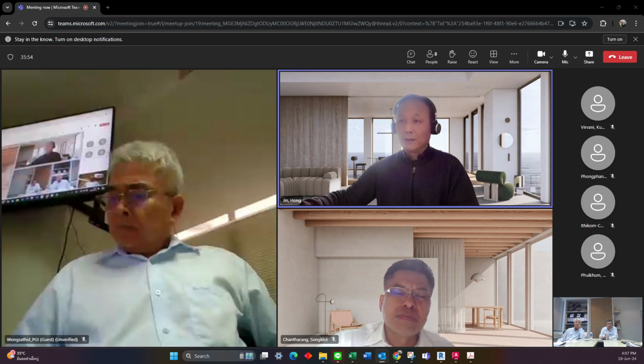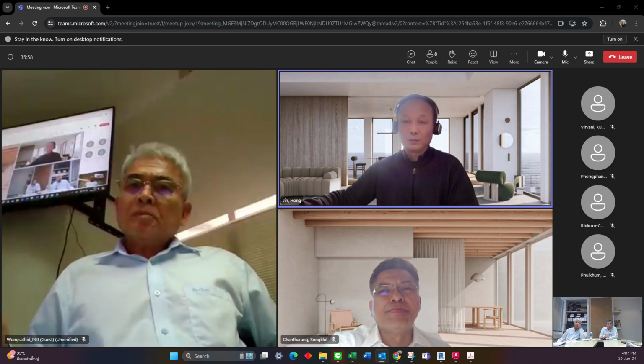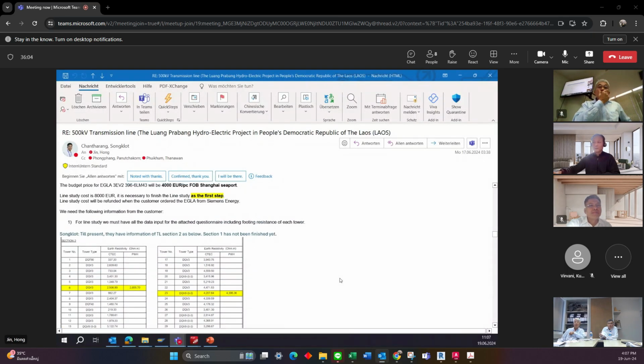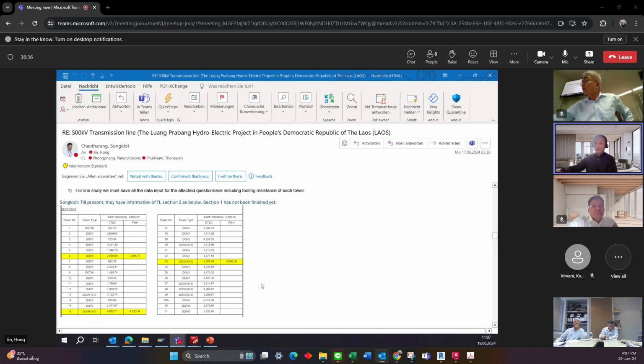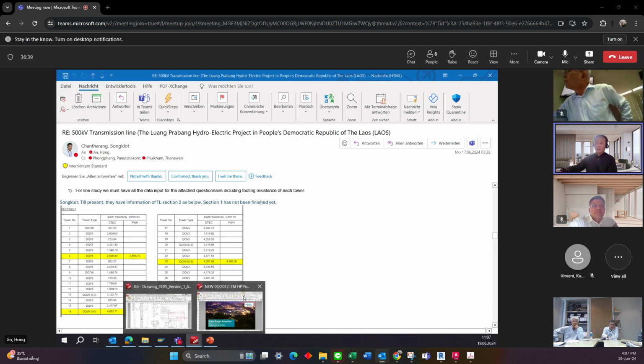Let me share now the reply from the customer side. We have a questionnaire for the line study. As I mentioned, the line study is the mandatory first step. We have so many towers on this transmission line, and for each tower we need the footing resistance, geometry, dimensions of the surge arrester, and also the technical specification of the conductor as well as the insulator itself. Those data will be needed as input for our line study.